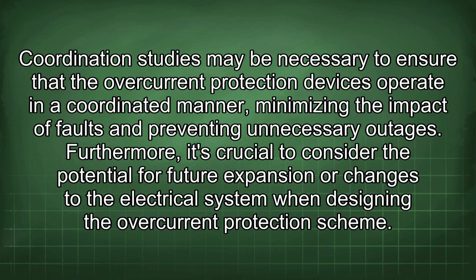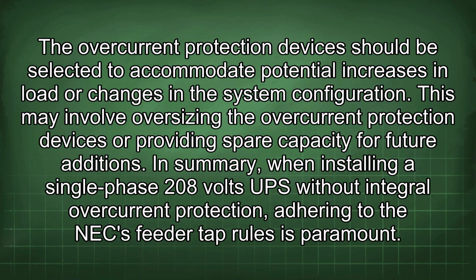Coordination studies may be necessary to ensure that the overcurrent protection devices operate in a coordinated manner, minimizing the impact of faults and preventing unnecessary outages. Furthermore, it's crucial to consider the potential for future expansion or changes to the electrical system when designing the overcurrent protection scheme. The overcurrent protection devices should be selected to accommodate potential increases in load or changes in the system configuration. This may involve oversizing the overcurrent protection devices or providing spare capacity for future additions. In summary, when installing a single-phase 208-volt UPS without integral overcurrent protection, adhering to the NEC feeder tap rules is paramount.